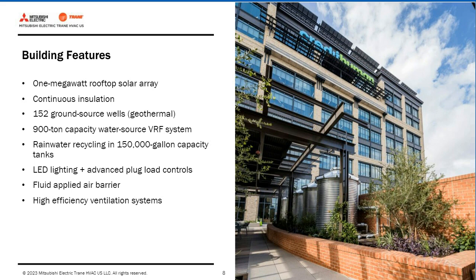So starting from the ground up, though, on some of the key sustainability features of the building, we've got 152 geothermal wells. They're approximately 300 feet deep. From a resiliency standpoint, this is really key. For those of you who already designed ground source systems, I don't have to tell you why. These systems are much more commonly in use in very cold climates because we have a stable source heat exchange in the ground.